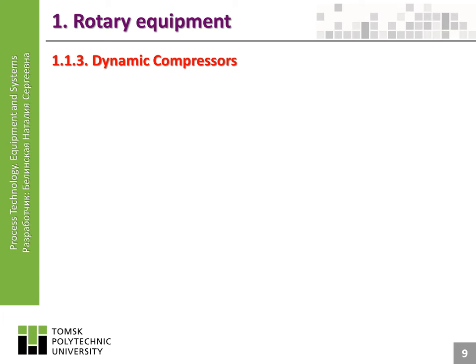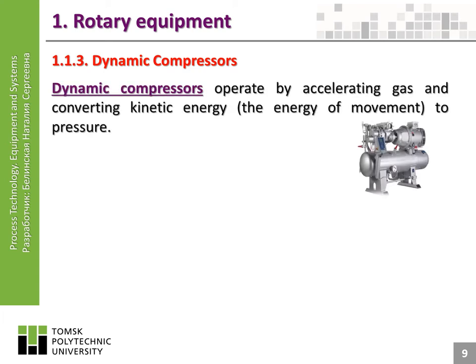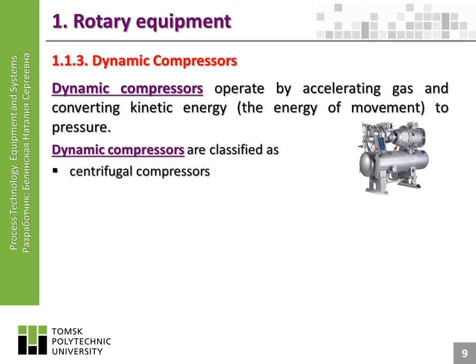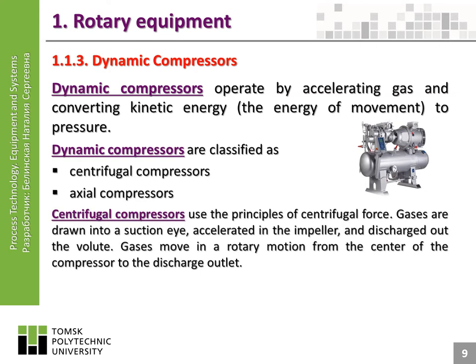Dynamic compressors operate by accelerating gas and converting kinetic energy — the energy of movement — to pressure. Dynamic compressors are classified as centrifugal compressors and axial compressors. Centrifugal compressors use the principles of centrifugal force: gases are drawn into a suction eye, accelerated in the impeller, and discharged out the volute. Gases move in a rotary motion from the center of the compressor to the discharge outlet.